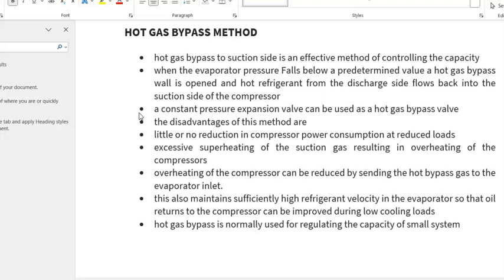A constant pressure expansion valve can be used as a hot gas bypass valve. The disadvantages of this method are little or no reduction in compressor power consumption at reduced load, and excessive superheating of suction gas, resulting in overheating of the compressor.